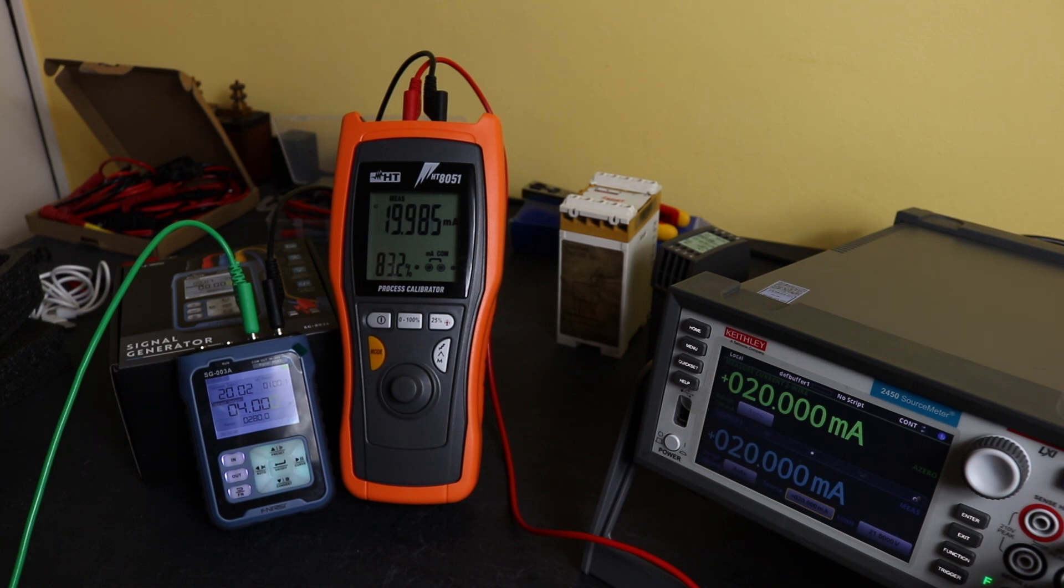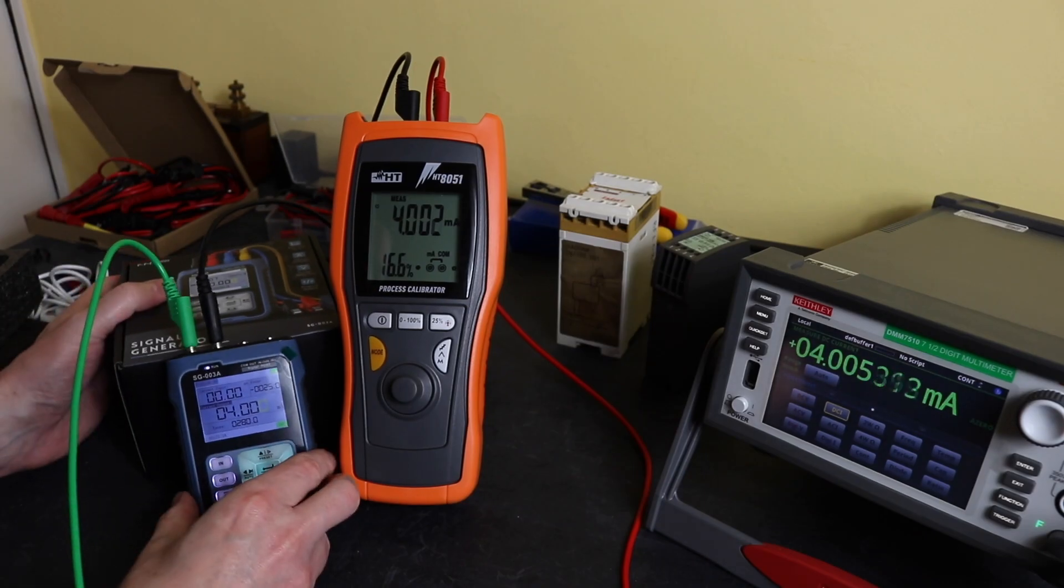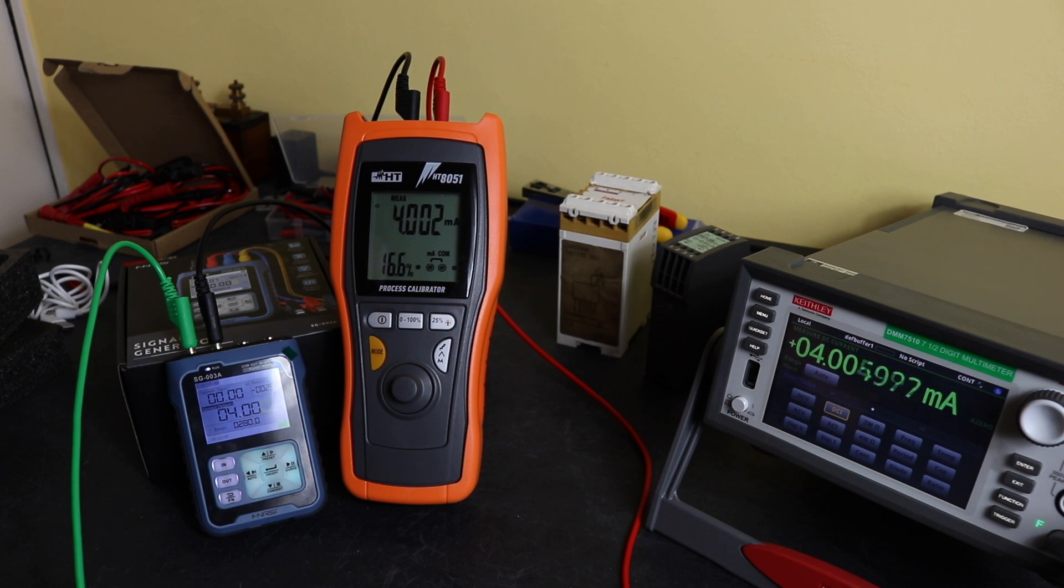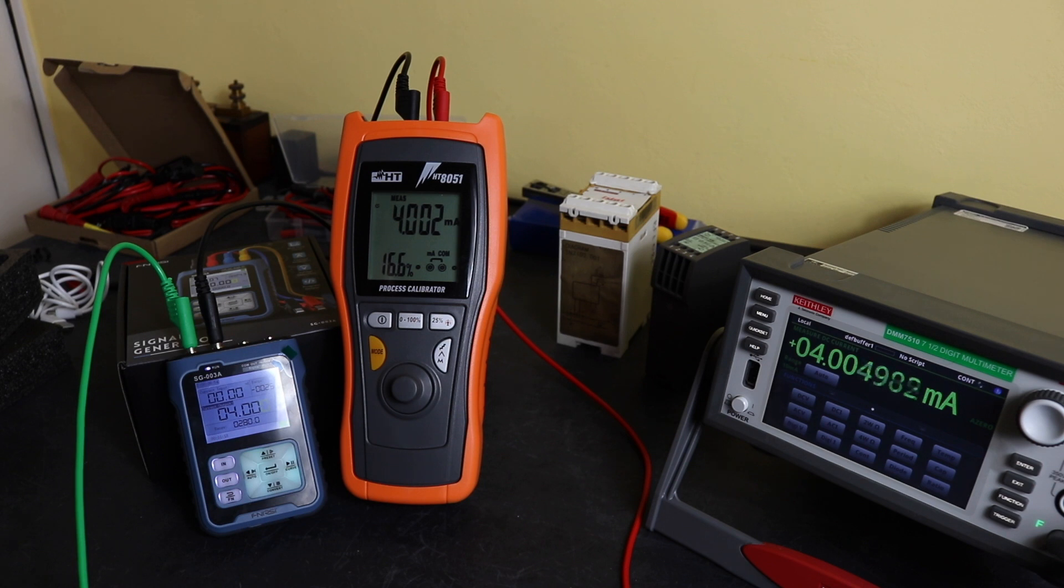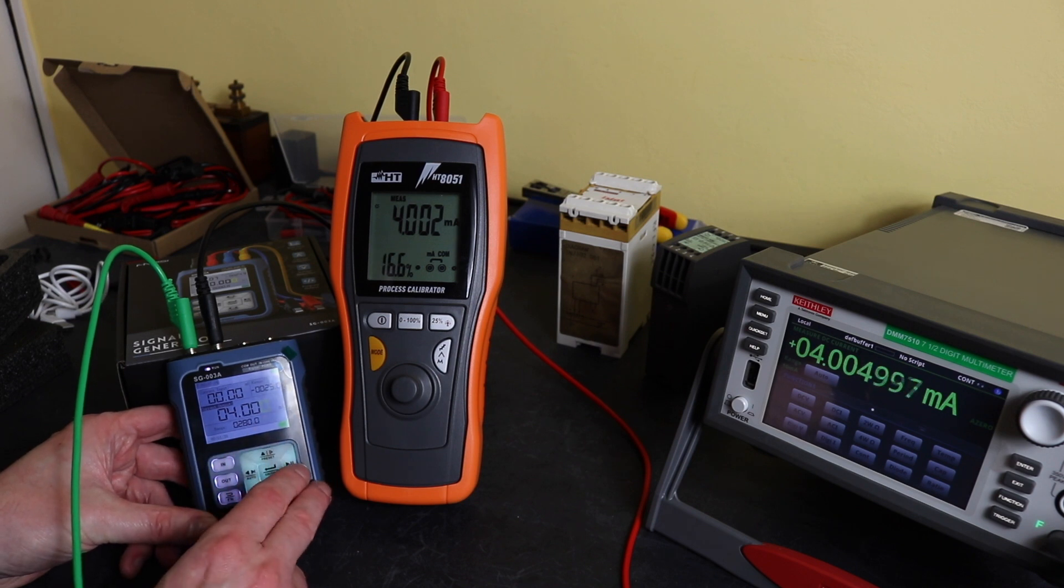Okay, so we've switched things around. We've got our multimeter now running on amps, that's picking up 4.005 milliamps at the moment. We've left our HT8051 reading as well, so that's reading 4.002 this time, and the FNIRSI says we're putting out exactly four milliamps.